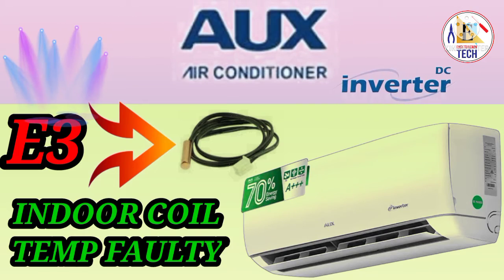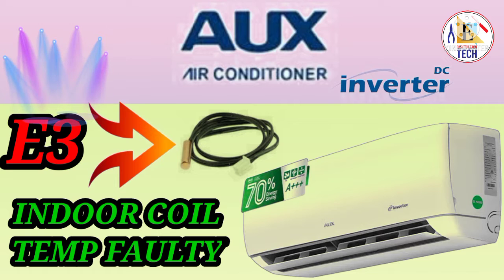Let's see the next error code. When you see E3 on your display, it means the indoor coil temperature sensor is faulty. In our indoor unit, as you can see in this picture, the same coil sensor is installed in your indoor unit also, which protects against ice forming on our coil.